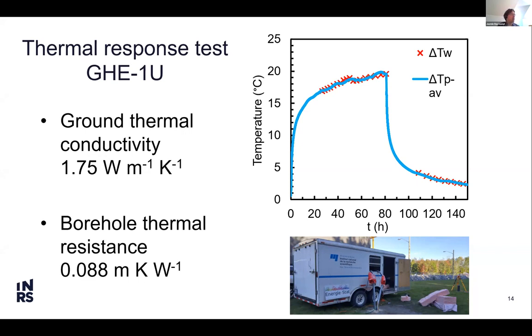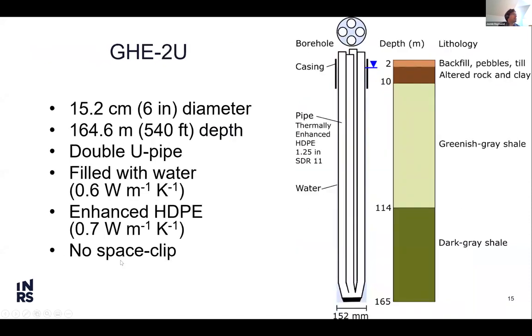What we found was a ground thermal conductivity of 1.75 watts per meter Kelvin, so it's not a very high value. A good value would be above 2.5 watts per meter Kelvin, but that's basically what shales from a sedimentary basin give you. And a borehole thermal resistance of 0.088 meter Kelvin per watt. That's an interesting value, I would say an average value, characteristic of a single U-shaped borehole. A similar borehole with a 6-inch diameter would have a slightly higher value, near 0.1 meter Kelvin per watt. So the smaller diameter reduced the thermal resistance a little bit, but it's pretty much an average value for these kinds of systems.